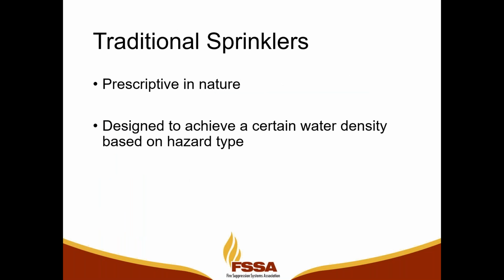So when we talk about traditional sprinklers, because they've been used since 1887, people have a lot of familiarity with sprinklers. They tend to be prescriptive in nature when you look at FM approvals or NFPA 13 or anything else. They're basically designed to achieve a certain water density based upon a certain hazard type. Typically, they'll tell you you need a density of like 0.3 GPM, and that will be prescriptive for various different types of applications or hazard types. Next slide.